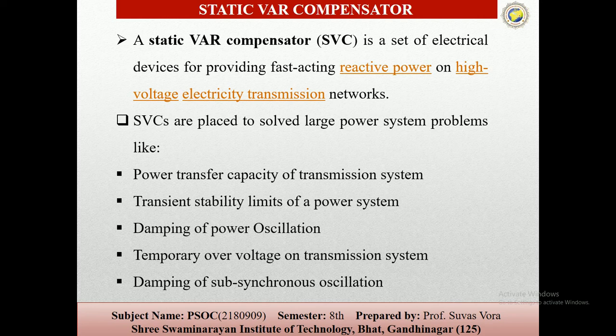So in the industries, the SVCs are placed near the high and rapidly varying loads, such as the arc furnace, where the voltage flicker is reduced by the SVC, and the temporary overvoltages are absorbed by the SVC to get the voltage control of the systems.